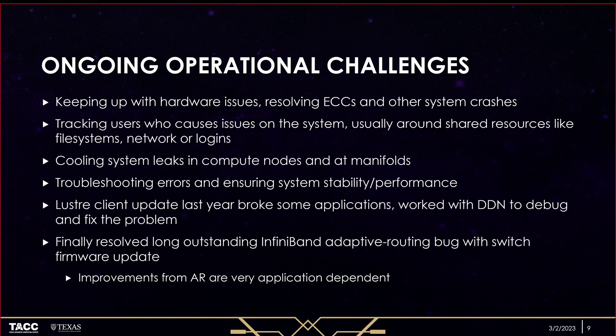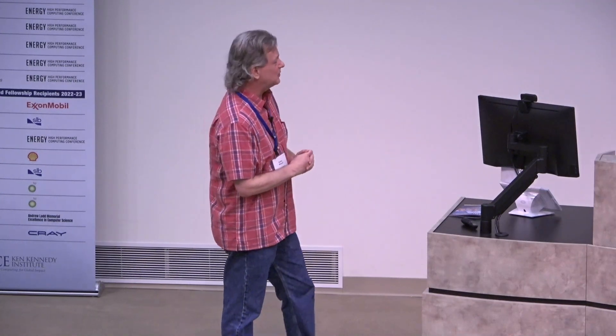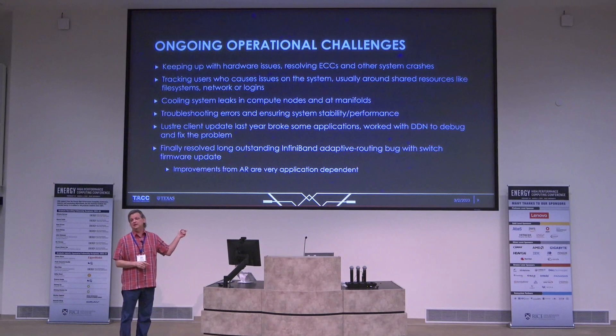Our usual operational challenges: we've had fewer file system interruptions this past year due to users doing bad things. Almost always when something happens on the file system, it's usually some user doing something bad. The bigger issue I want to spend a few minutes on is the cooling system leaks. The system was supposed to be designed with zero leaks, but unfortunately we had some bad seals manufactured on some of our cooling blocks. We've had to replace about 500 out of the original 8,000 nodes so far.